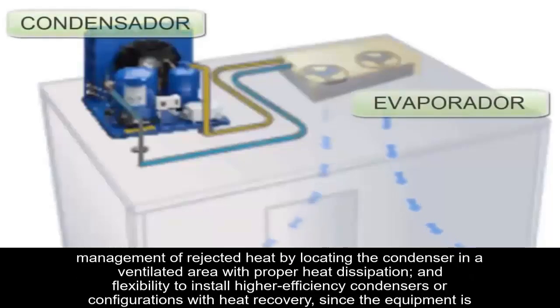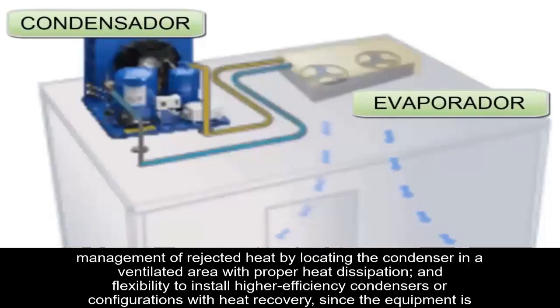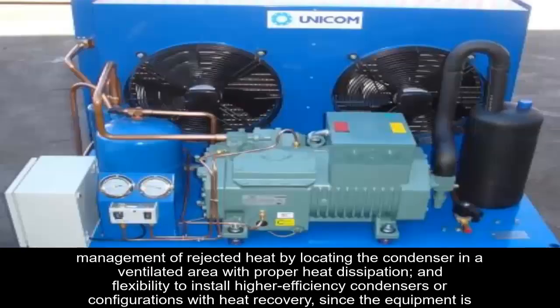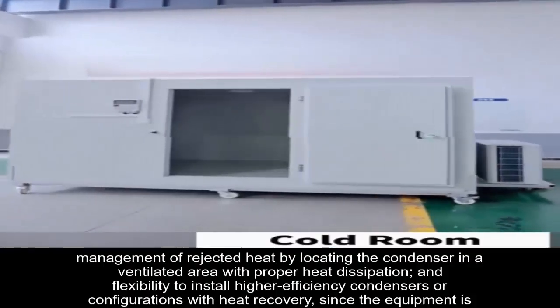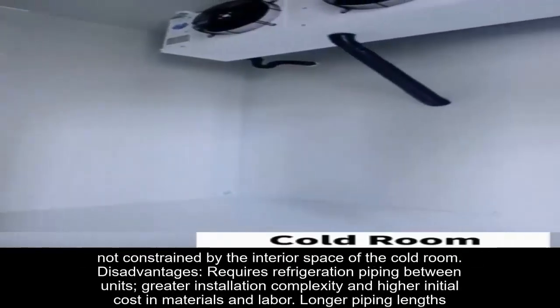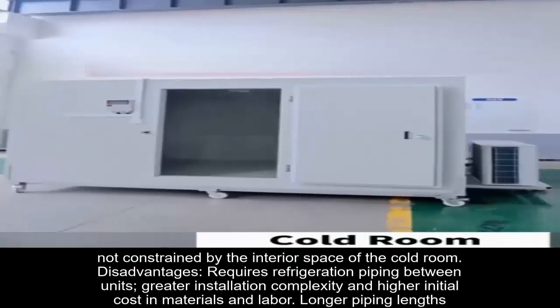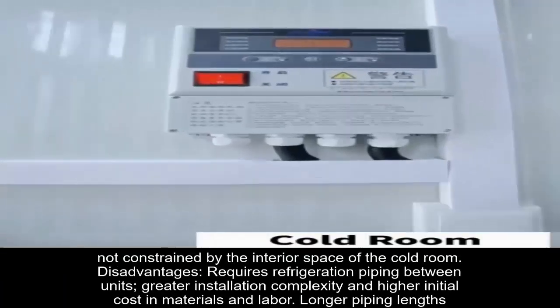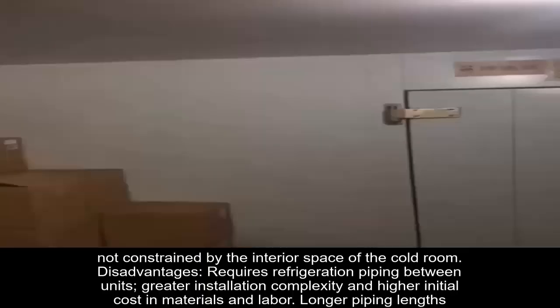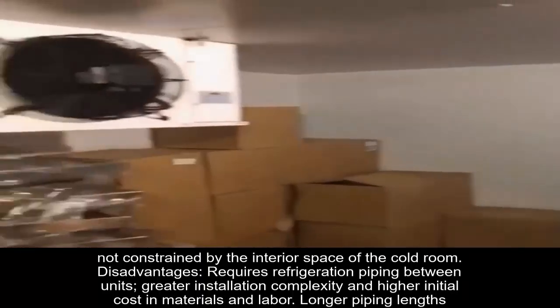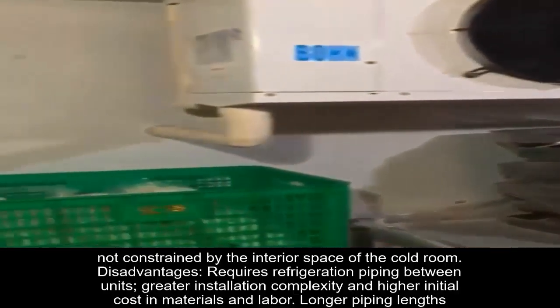Better management of rejected heat by locating the condenser in a ventilated area with proper heat dissipation, and flexibility to install higher efficiency condensers or configurations with heat recovery, since the equipment is not constrained by the interior space of the cold room. Disadvantages, limitations: requires refrigeration piping between units, greater installation complexity and higher initial cost in materials and labor.